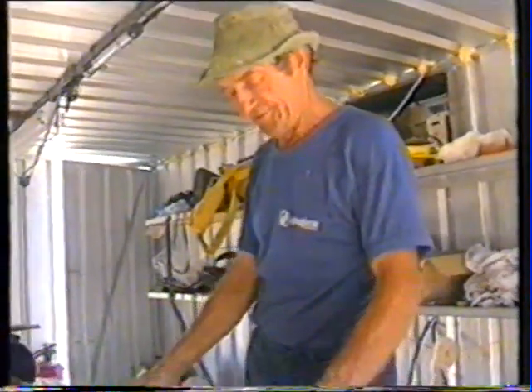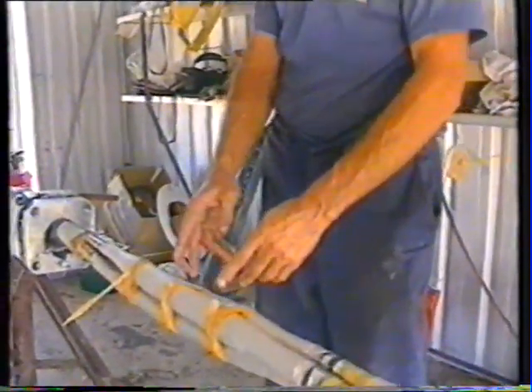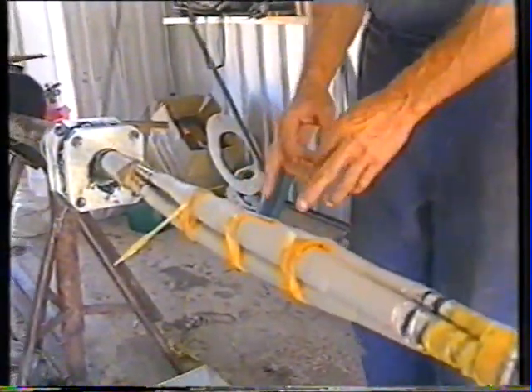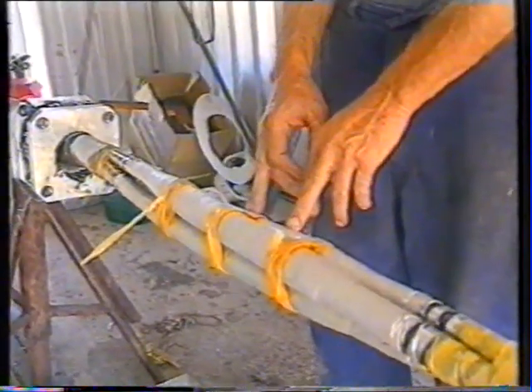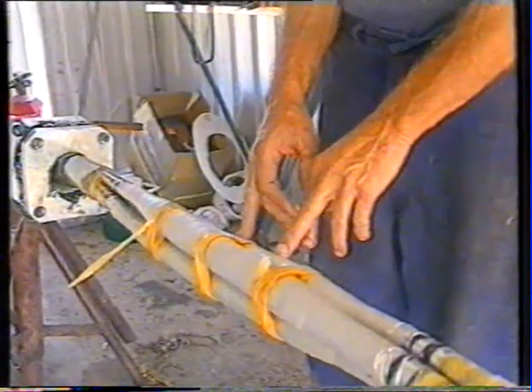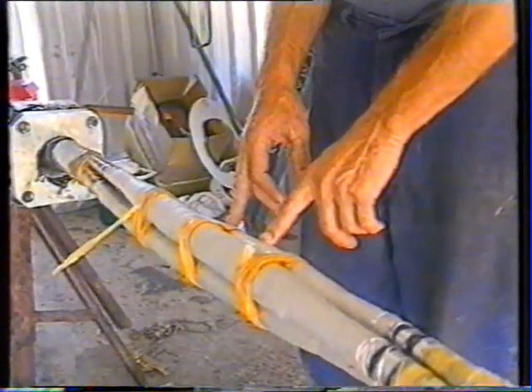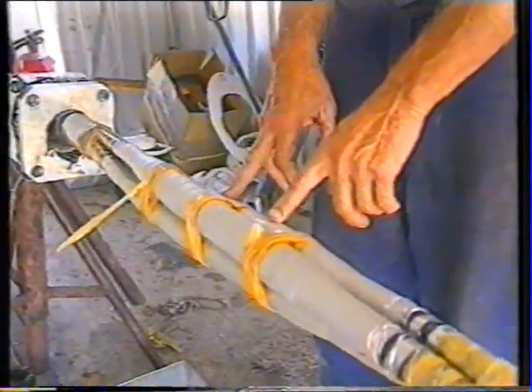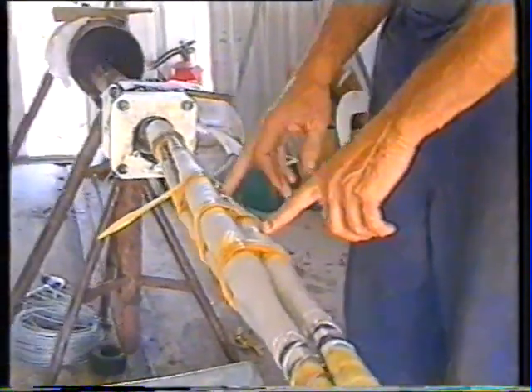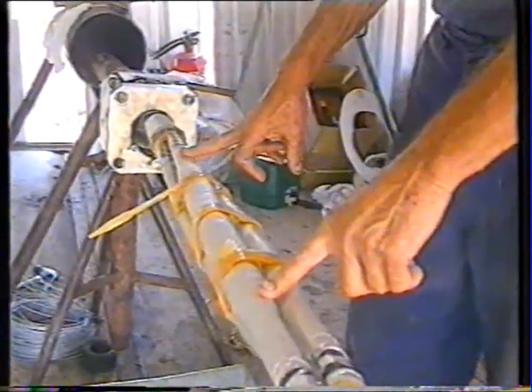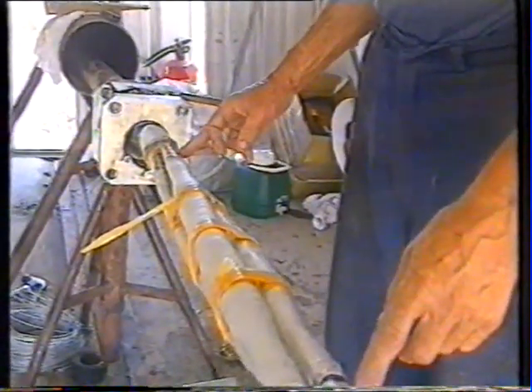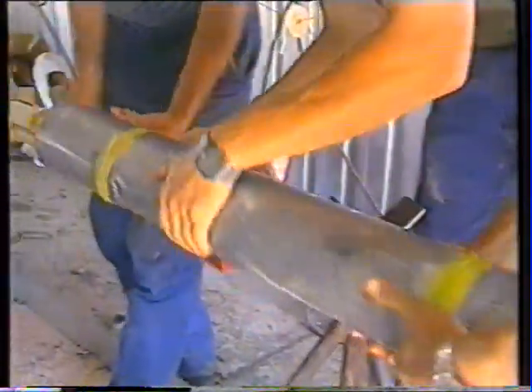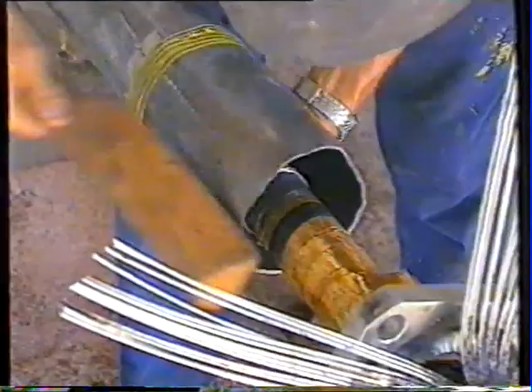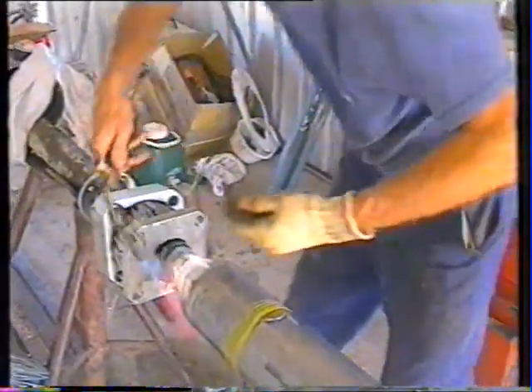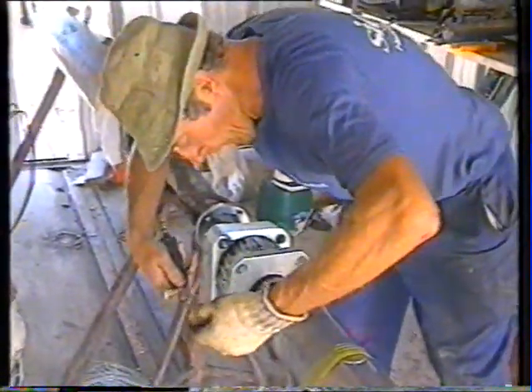What we've got, we've got two ends of the cable. So to join them together, we put ferrules in the middle. We sweat the ferrules, clean them, close them up, and then we insulate them. Bring the insulation up to the size they require on the drawing, then we put the screening over. Bind the screenings together at both ends of the cables. And then after that, we slide the lead sleeve in, over, and we wipe the two ends. And we bring the bronze foil up to the wipes and re-wipe again at both ends.